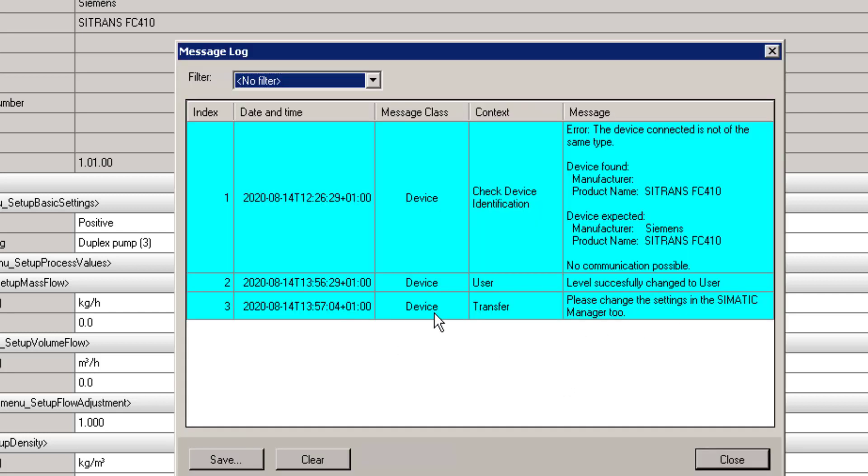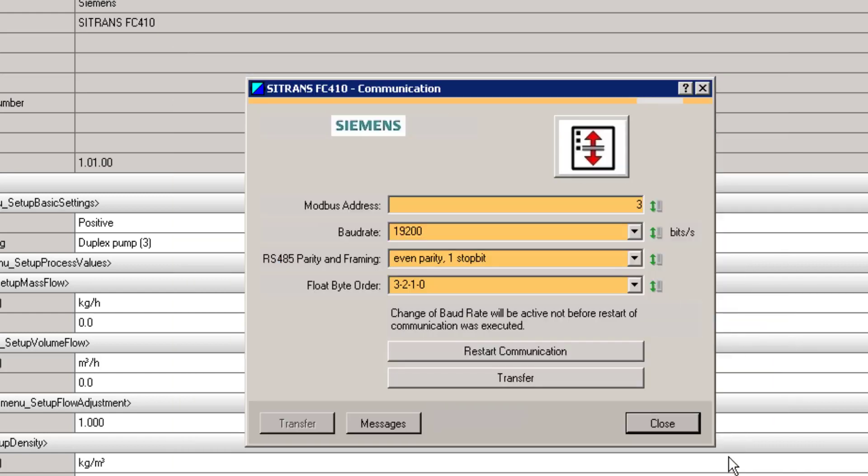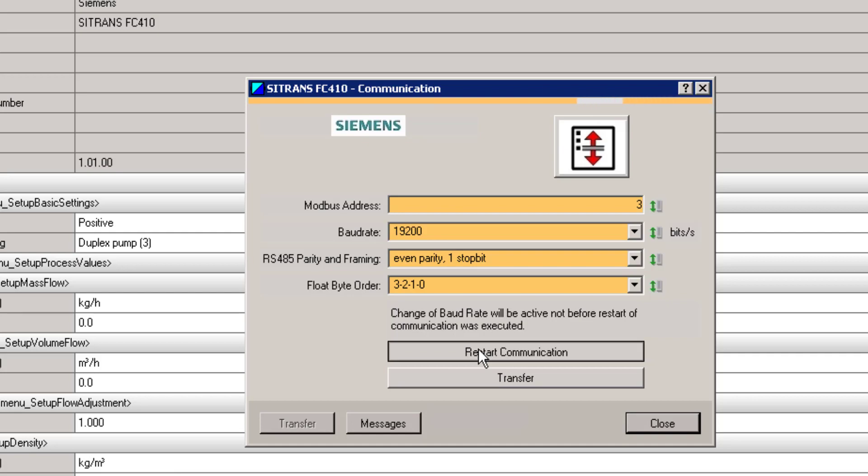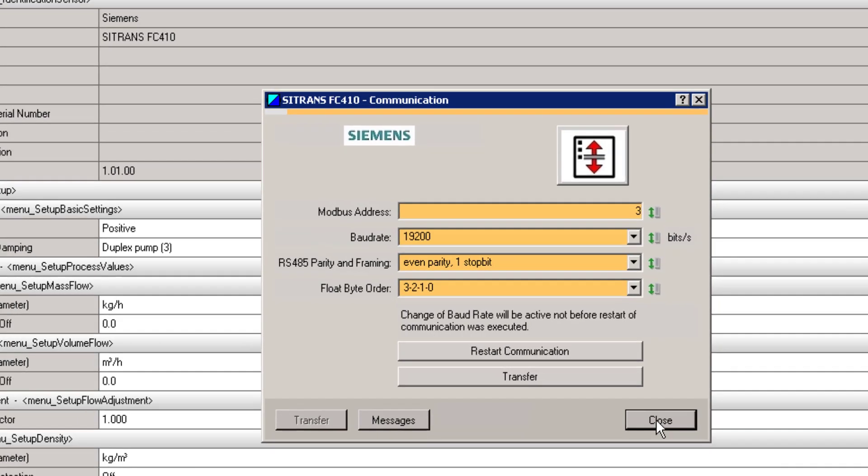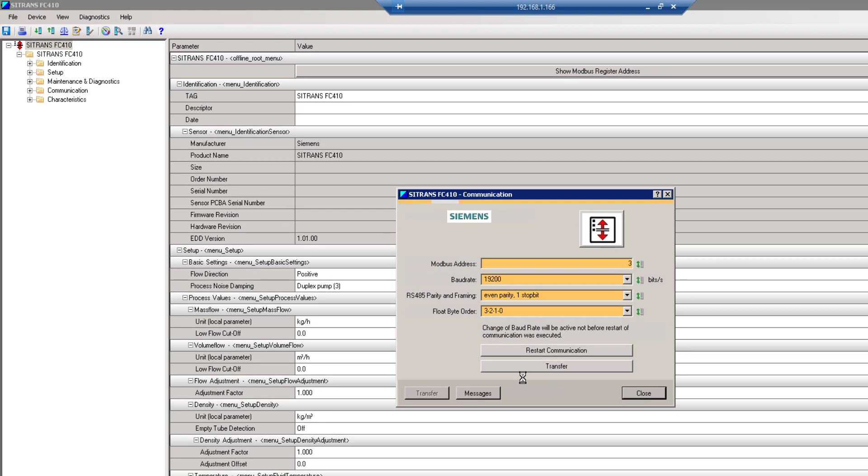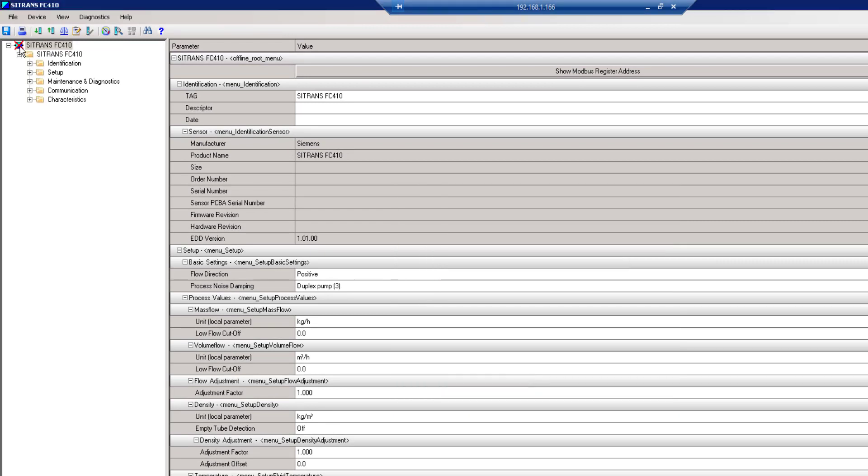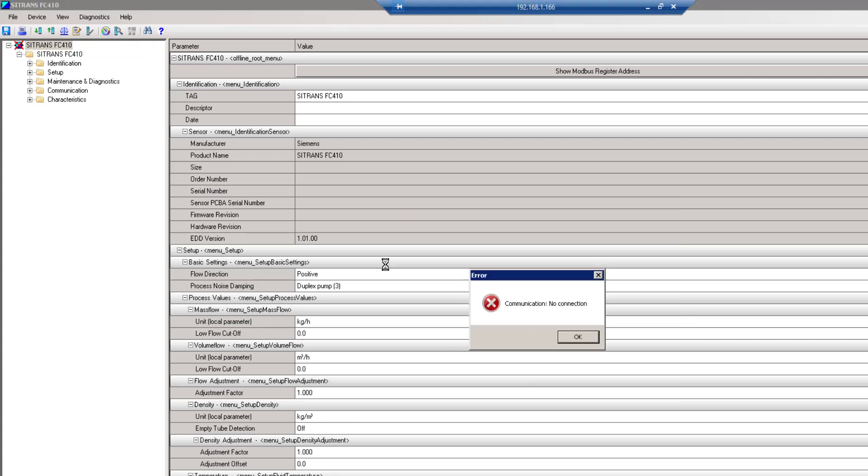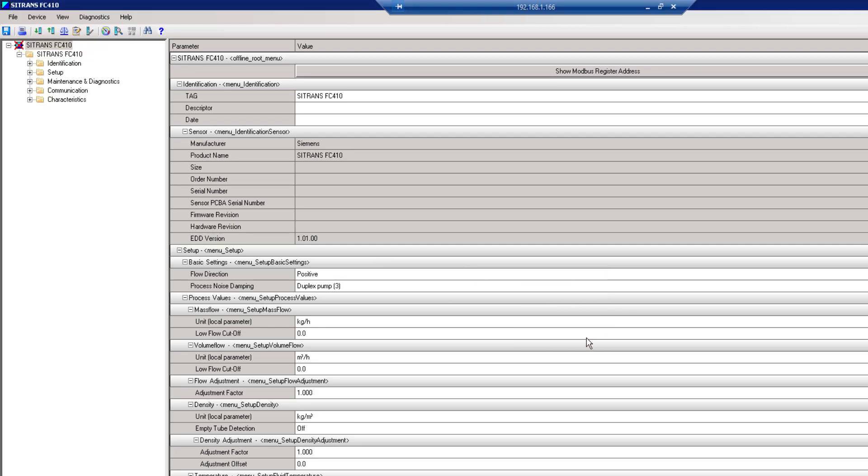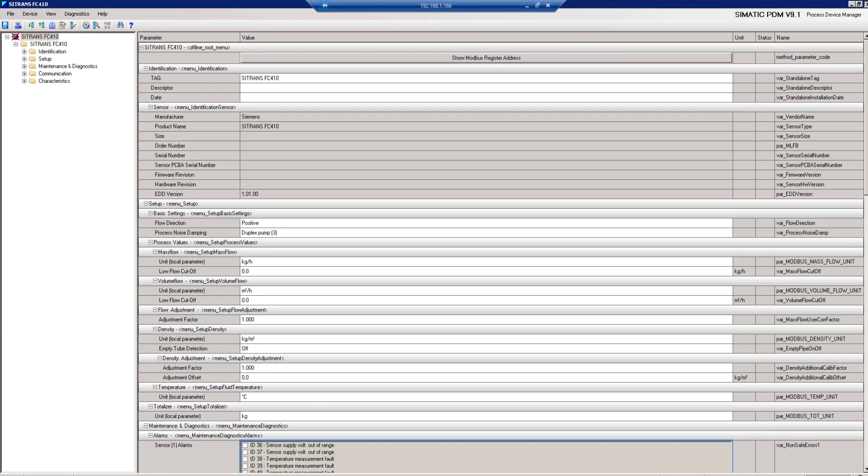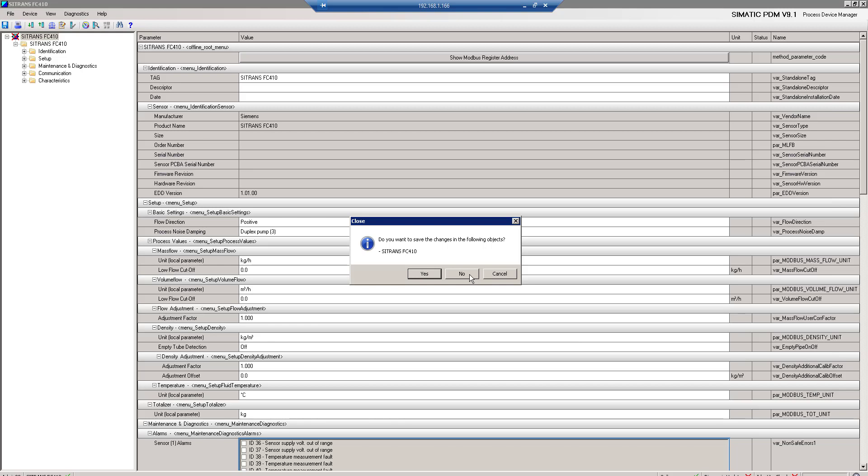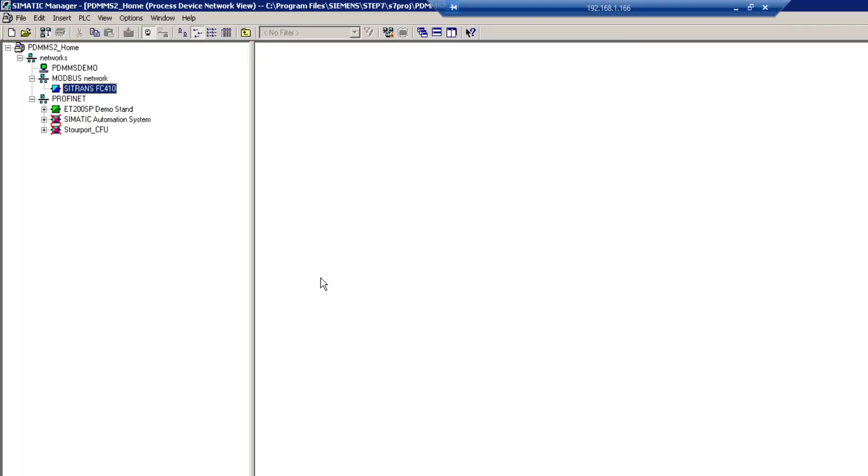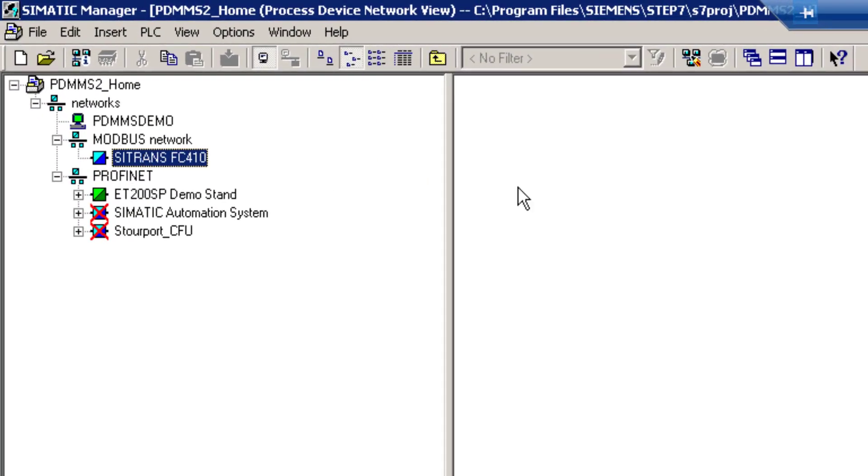It's saying here, please change it in my Simatic Manager too. Because when I restart my communications, it's set up to talk to device one. When I click on this restart communication, it's now set to address three. So you can see up here, look I've lost comms. If I try to go online, I get communication, no connection. So what I have to do is come out. You do have to close it at this stage. Go back into my project here. So this is what it's talking about. Back in Simatic. This is Simatic Manager.